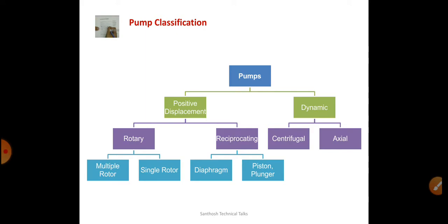If we arrest the outlet, pressure is added on the fluid elements, and we know that pumps are generally used for pumping liquids, which are incompressible in nature. If we close the outlet valve of a positive displacement pump, the pump will get damaged by the compression of the liquid particles.